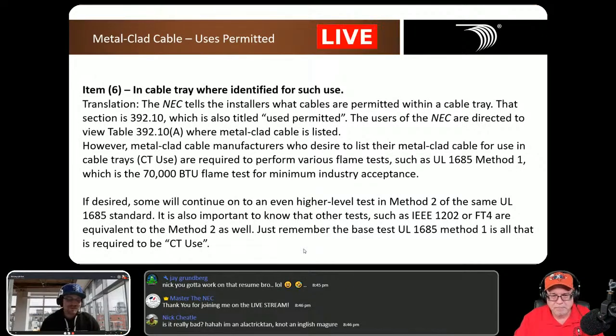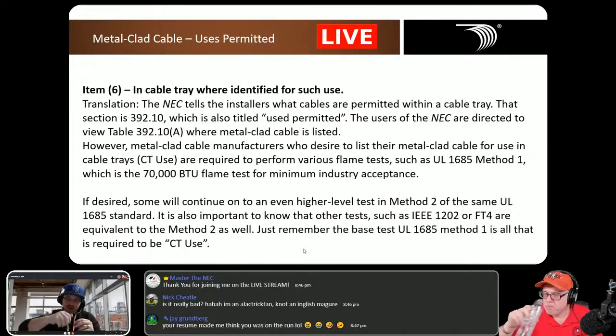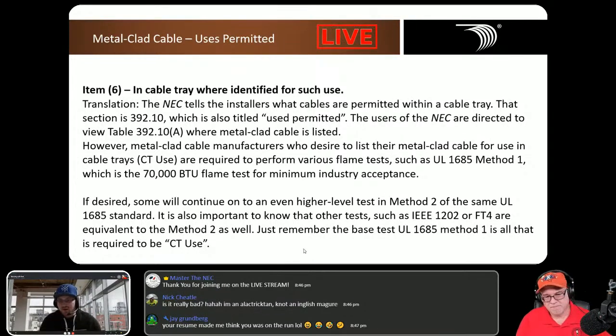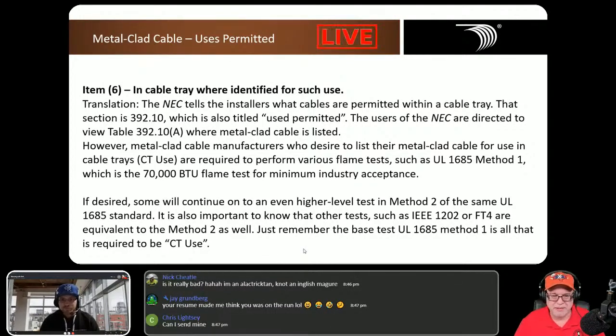I did a service call a few days ago where they had a 4-square box behind the double oven. The customer pulled out the double oven and opened up the 4-square blank cover, and it was 6-4 SER aluminum, spliced with the bigger blue wire nuts, not a special aluminum-to-copper connector, and the leads from the double oven were copper. So they took their 6-4 SER aluminum to the whip from the double oven, copper, and just put it in a blue wire nut, and it actually burnt. We have dissimilar metals going on, and that's a potential weak point there. So definitely not a good thing to do. It burned up the blue wire nut, for sure.